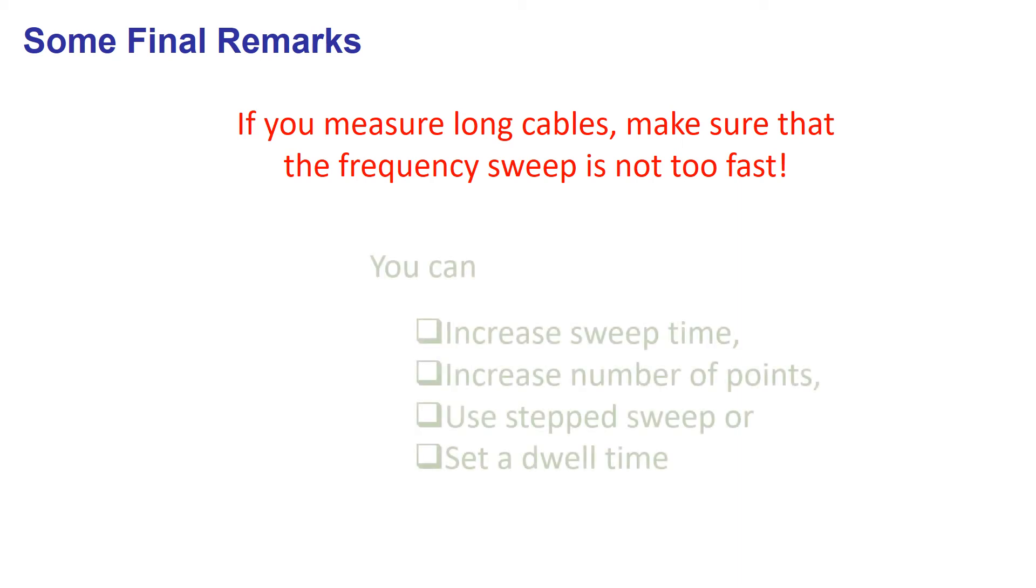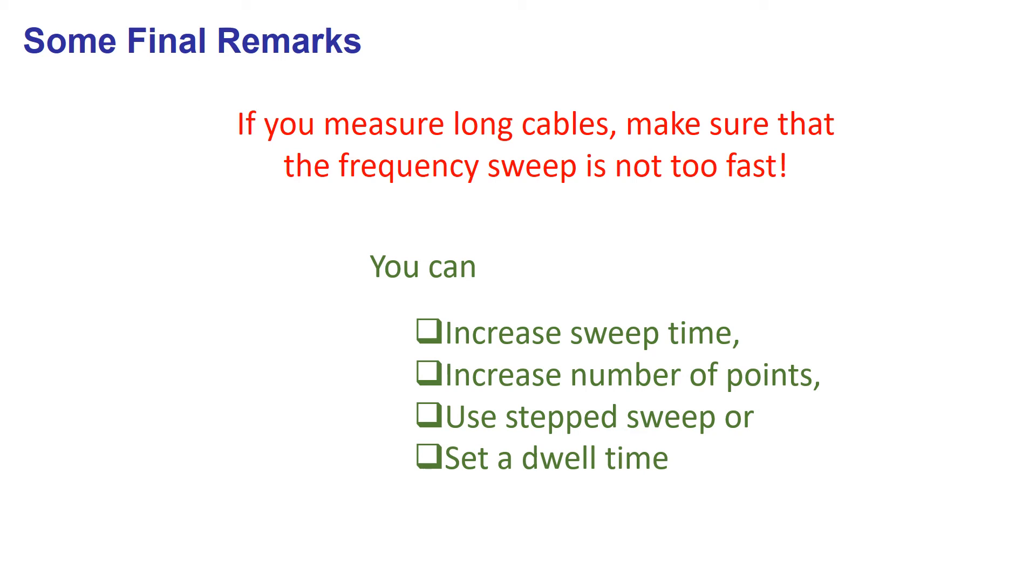You can reduce the sweep speed by, for instance, increasing the sweep time, or increasing the number of points, or you can also use a stepped sweep or set a dwell time.